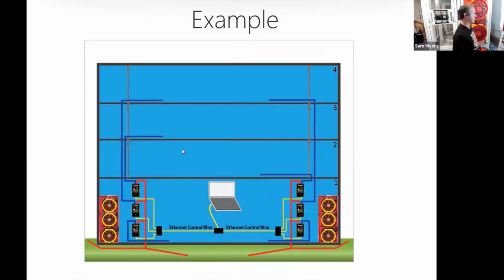All those reference pressures get fed into our one test station, and in the software we'll be able to see, once we do a test run with our fans, if we're getting a good unified pressure throughout. You want to measure as many floors as possible, and if you're getting into a 15-story building, you may go every 2 floors. As long as you're getting a good sample throughout, you'll be able to see that in the software.